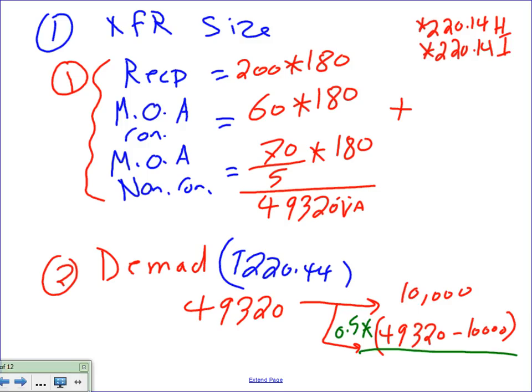If you do all the math, you end up with 29.6 kVA. And remember, I divided by 1,000. The first 10,000, don't forget to add it. The first 10,000, leave it alone. Anything higher than 10,000 multiplied by 0.5, then add them up. Add the 10 to the stuff that you cut by 50%. That will get you 29.6 kVA. I moved into kVA now, but we know how to move from VA to kVA: divide by 1,000, right? Any question, guys, about 29.6 kVA?